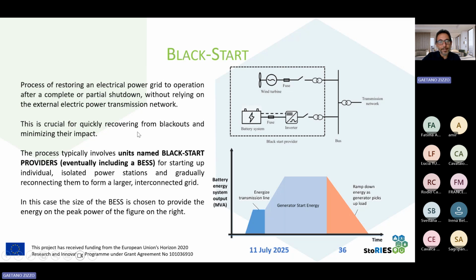So for restarting the system after the blackout, we typically involve units named black start providers that can include battery storage systems, like in the case represented here. These black start providers start up individually isolated power stations and gradually reconnect them to form a larger interconnected grid. In this case, the size of the BESS is chosen to provide the maximum power that the generator that has to be started needs to start, and to provide the energy that is the area of this diagram.